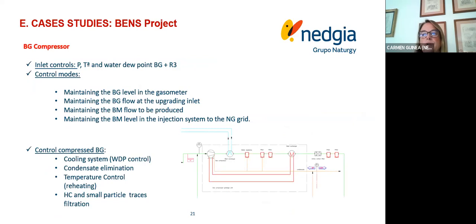Pressure, temperature, and water dew point are the main inlet control points before the gas gets into the compressor. The upgrading plant, and therefore the compressor, could be controlled in 4 different ways. Maintaining the biogas level in the gasometer, in case, for example, you have motors consuming from the gasometer. Maintaining the biogas flow at the upgrading inlet. Maintaining the biomethane flow to be produced, or maintaining the biomethane level in the injection system to the natural gas grid.